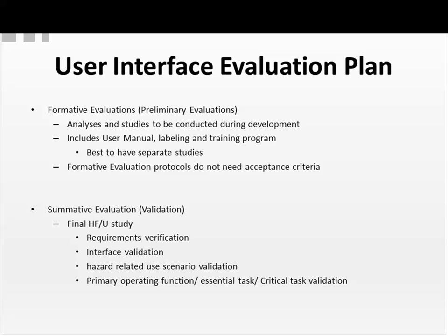Now, an important point is that the formative evaluations or preliminary evaluations, the protocols, you must have protocols, but you do not need acceptance criteria. The point of these evaluations is to learn and to factor those learnings back into the design program. So these do not need acceptance criteria as typically technical evaluations would.